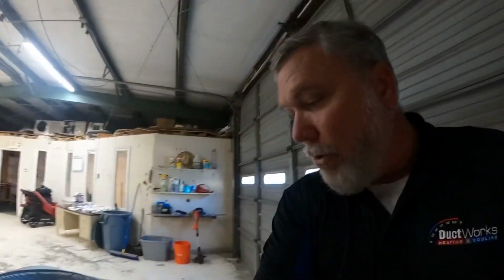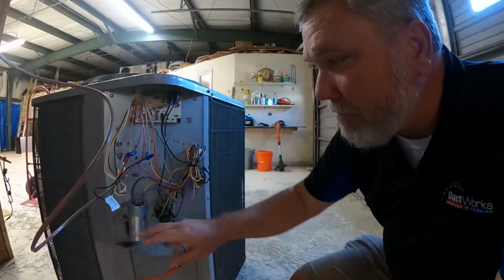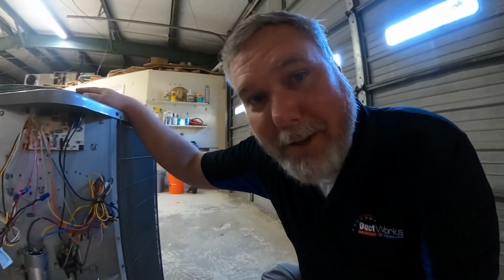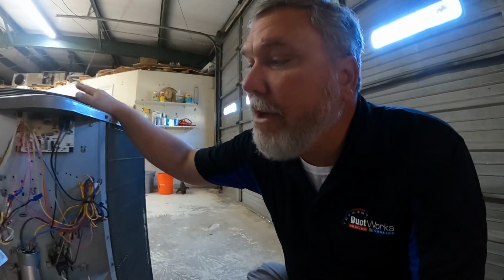Also, we go through the outdoor unit's controls. For example, start capacitors. You might have heard people talk about that. Yep, I had my start capacitor replaced. Well, there's a reason. When these capacitors go bad, they can cause a compressor to fail. It can cause the fan motor outside to fail. So when we go through these systems, we check the capacitors, and we don't just look at it and say, "Oh, well, it looks bad." We actually have instruments that can test the effectiveness of that capacitor. So it's very important. Replacing that capacitor can save you a bunch of money in the future on bad compressors, bad fan motors, and other components.